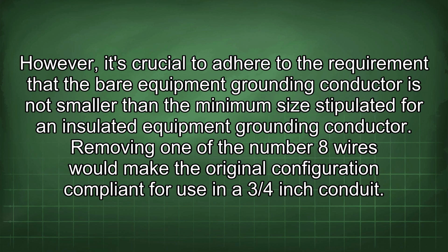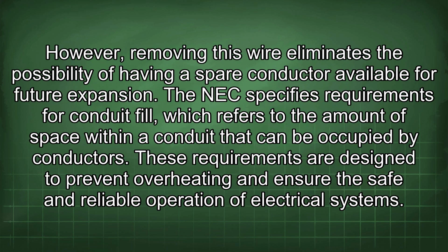Removing one of the number 8 wires would make the original configuration compliant for use in a 3/4-inch conduit. However, removing this wire eliminates the possibility of having a spare conductor available for future expansion.